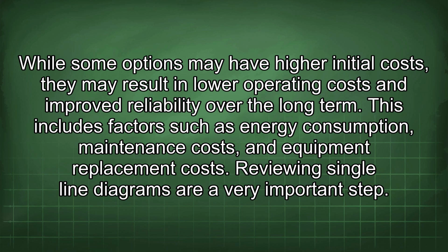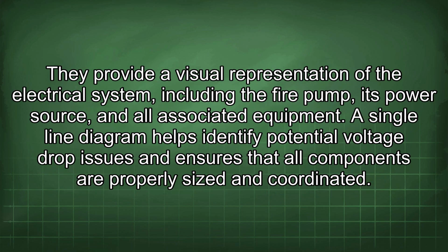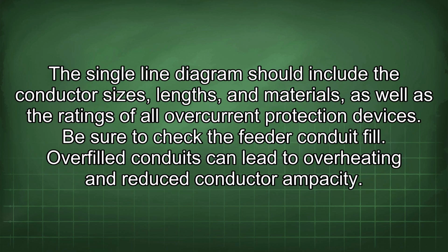Reviewing single-line diagrams is a very important step. They provide a visual representation of the electrical system, including the fire pump, its power source, and all associated equipment. A single-line diagram helps identify potential voltage drop issues and ensures that all components are properly sized and coordinated. The single-line diagram should include the conductor sizes, lengths, and materials, as well as the ratings of all overcurrent protection devices. Be sure to check the feeder conduit fill.